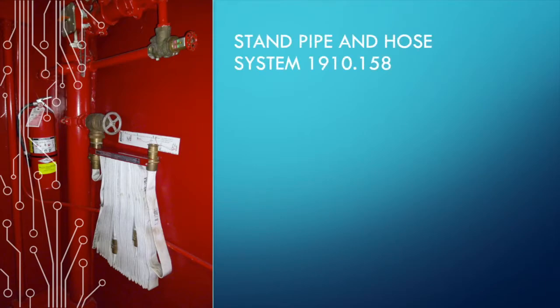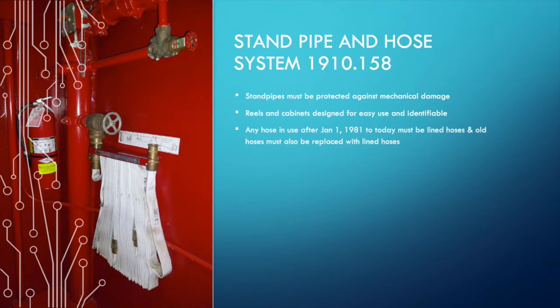Standpipe and hose system, 1910.158. Standpipes must be protected against mechanical damage. Reels and cabinets must be designed for easy use and easily identifiable. Any hose in use after January 1st, 1981 must be lined hose, and old hoses from before that must be replaced with lined hoses. No less than 30 psi at the nozzle, 200 gallons per minute for 30 minutes. Shutoff type nozzles must be used.